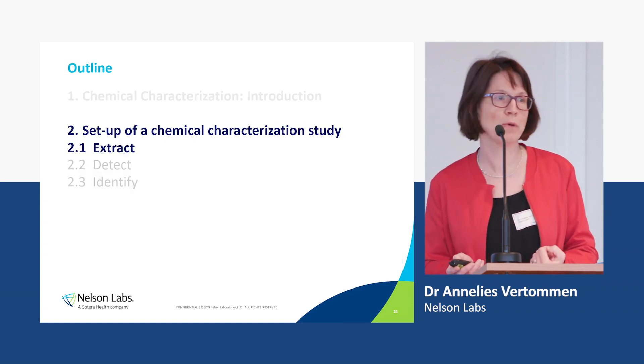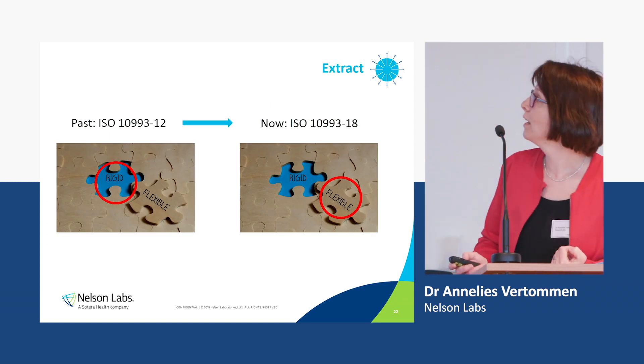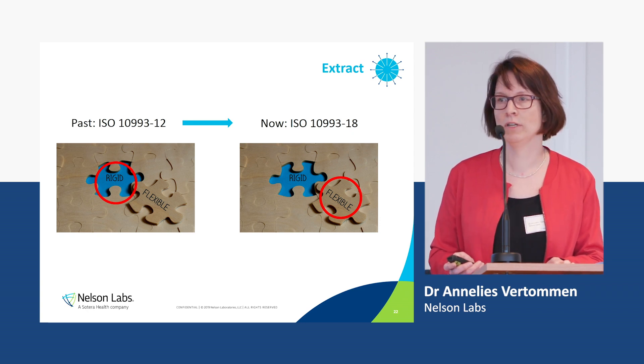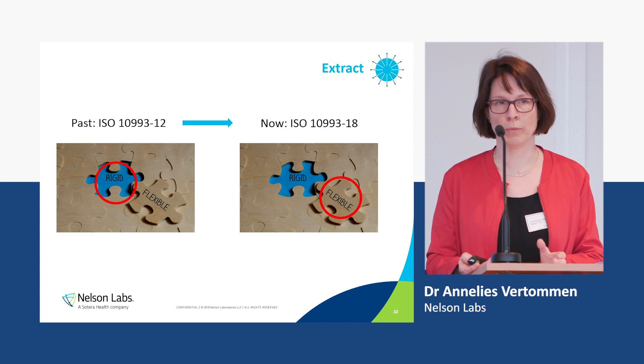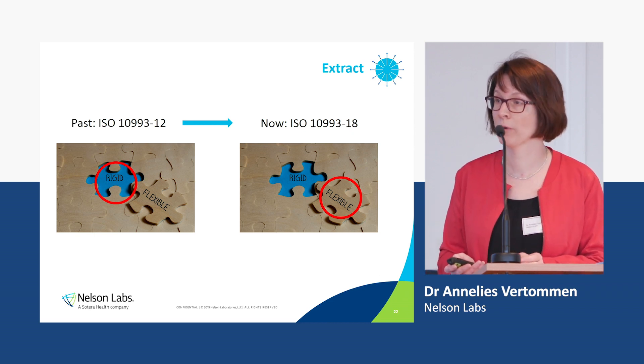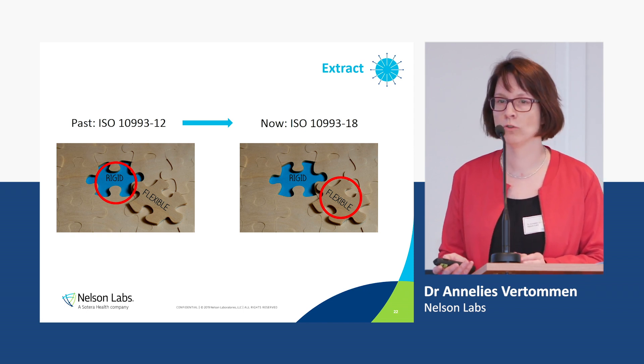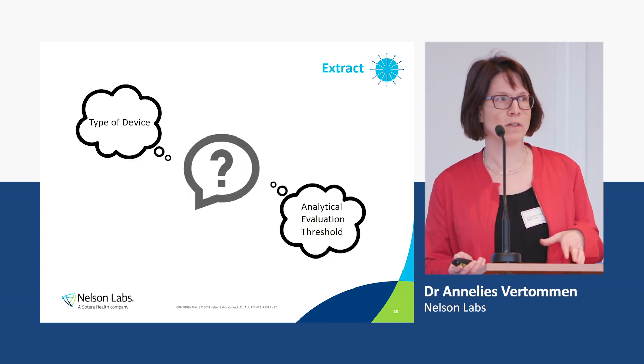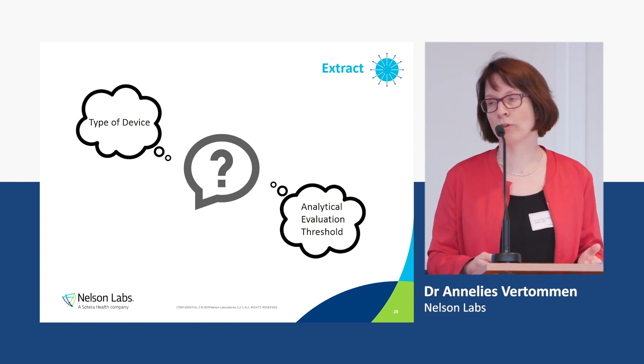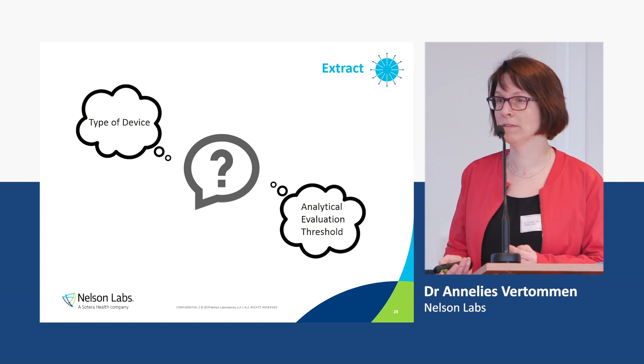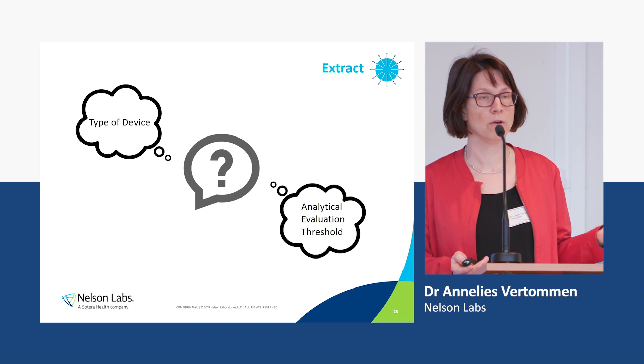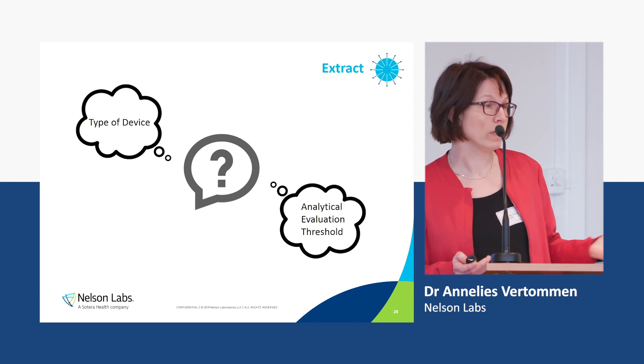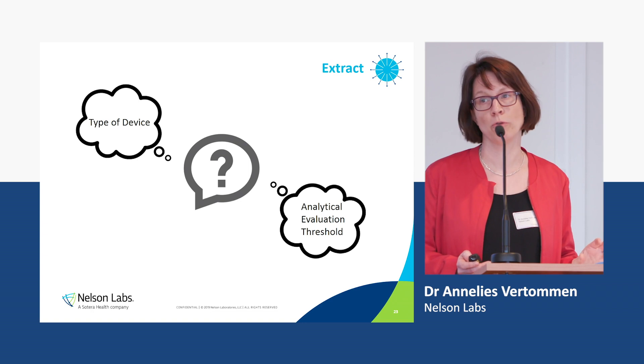Let's go to the first step: the extraction. In the past, the extraction was related to ISO 10993-12. But now, in the new dash-18, the sample preparation will be described completely in the dash-18, so you will not need to refer to the 12 anymore. The reason is that chemical characterization is a different type of study compared to all other biocompatibility tests, and it needs to be relevant for your medical device — so you have more flexibility to look at what your device is, how it's used, and what is the best setup.